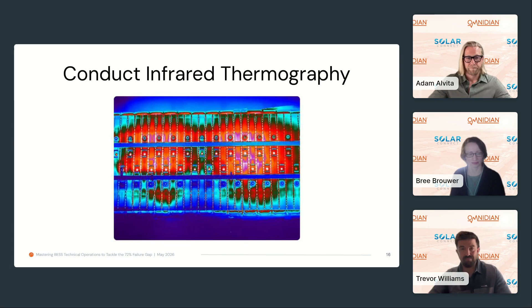Advanced risk management includes preventing slow degradation before a BMS alarm threshold actually triggers. You need to ensure your technicians measure the airflow and coolant flow rates, check the filters, and everything else, rather than just checking if an HVAC unit is quote-unquote on. There's an interesting crossover happening right now between the BESS world and the HVAC world, because both areas now need to work on these systems. In the future, we'll likely see more cross-training between HVAC and BESS technicians as the industry matures.